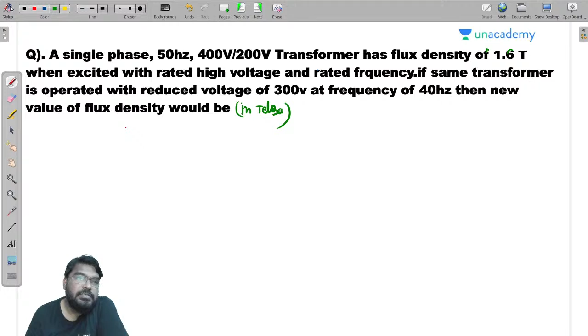Okay, how do we answer this question? A given transformer is 400 upon 200 volts, 50 Hz, with a maximum flux density Bmax1 equal to 1.6 Tesla. Supply is given to the rated high voltage side, so the high voltage is 400 volts and low voltage is 200 volts. So V11 is equal to 400 and frequency F1 is equal to 50 Hz. This is case 1.